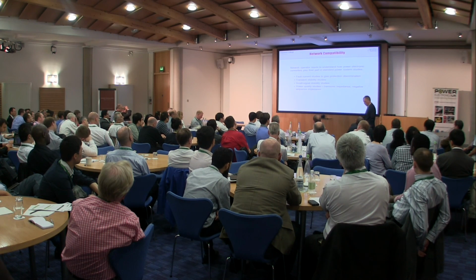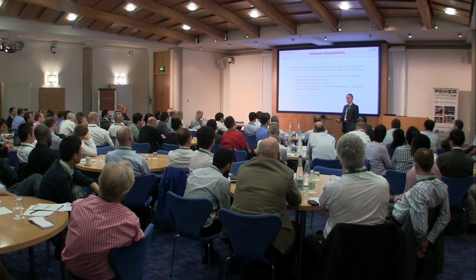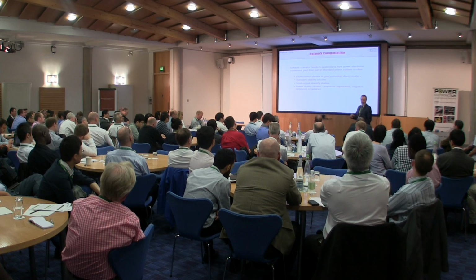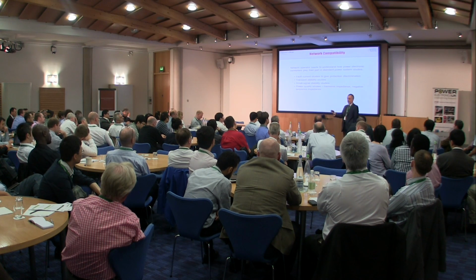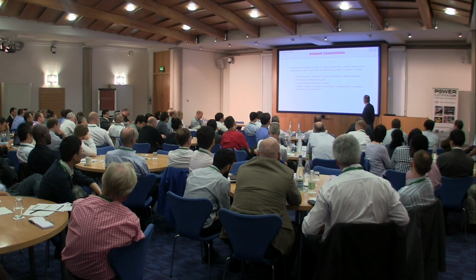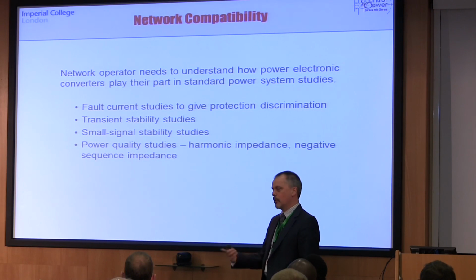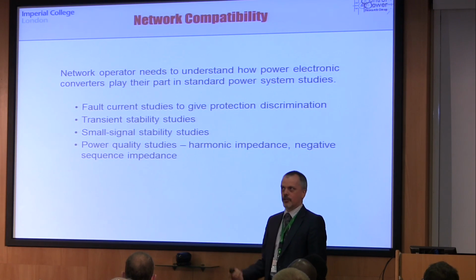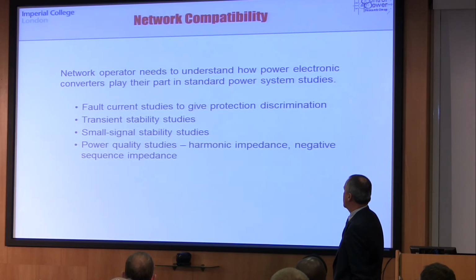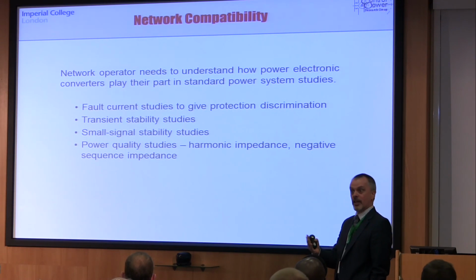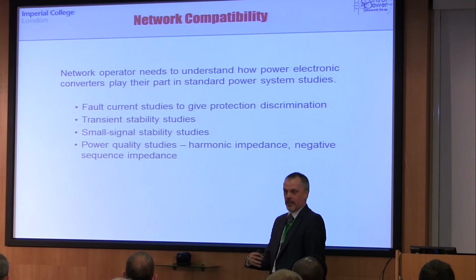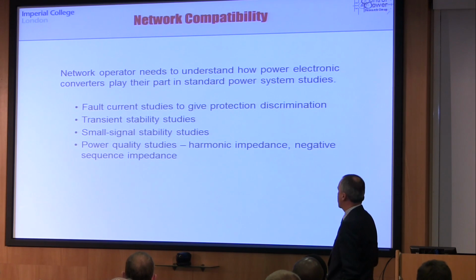A key thing for a power system planner to do is a protection study: how much fault current appears at various breaker and relay locations around the network when you throw various sorts of three-phase and single-phase faults, etc. Once they do a protection discrimination study, to make sure that the right breaker opens, it needs a fault current model. They need a transient model, so when there are large signal disturbances, we know the system is stable. Does it recover in a stable fashion from a fault? Is it prone to small signal stability issues? Are there control loop interactions, or interactions between the dynamics of different pieces of equipment, that give rise to problems?